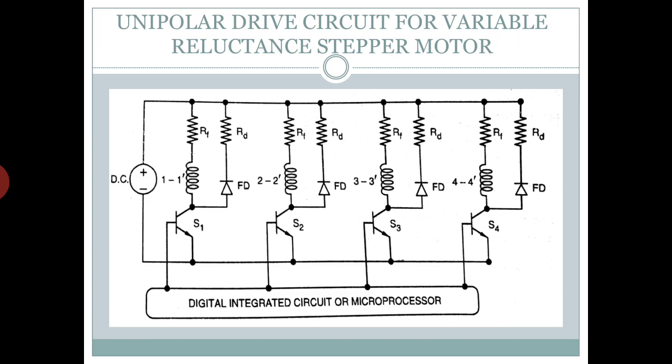The switching is done by pulses given by a digital integrated circuit or a microprocessor with an appropriate program loaded in it. As shown in the figure, a high value resistance Rf, known as forcing resistance, is connected in series with each phase winding so as to give a short rise time for the current to reach its desired value. A freewheeling diode along with a high value resistance Rd is connected in series with it for dissipating the energy stored in the inductive winding in the shortest period, minimizing the time for current to drop to zero.